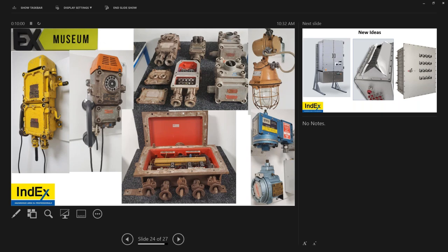Do you accept cable glands class 1 GR ABCD into a zone application? Well, the thing is, for North American glands, some of them don't even have that type of certification. No, I would not accept North American certified equipment meant for classes and divs into a zone application. But there are glands, CMP, CCG, the likes of these that are dual certified or tri-certified, ATEX, IECEx, and also for classes and divs.